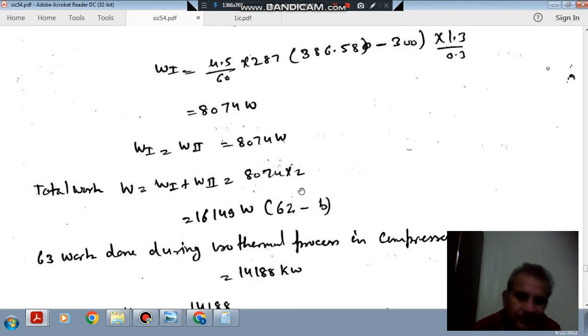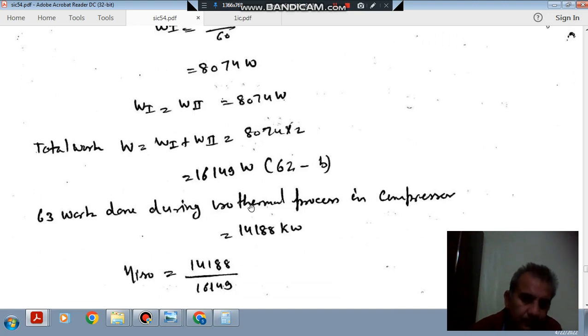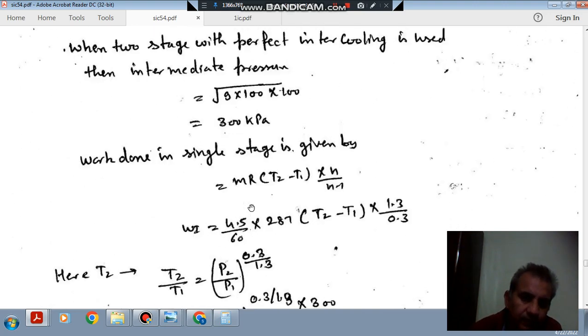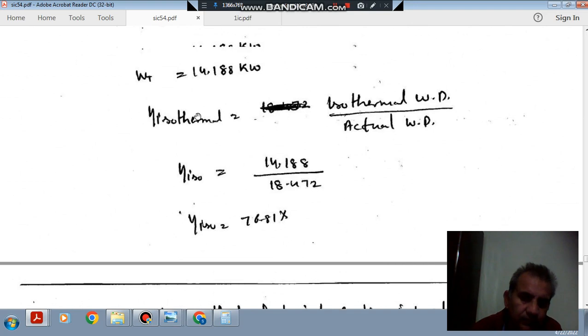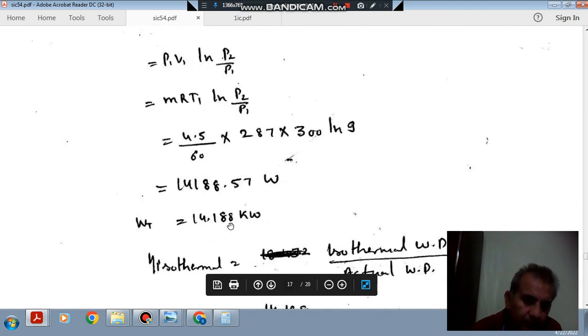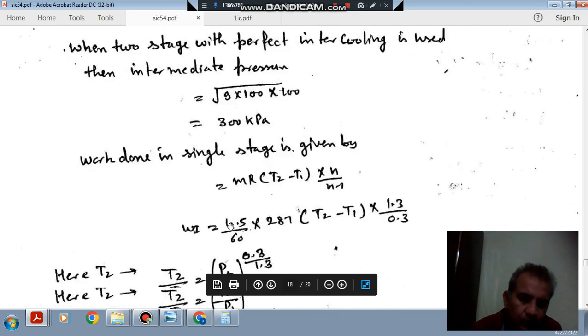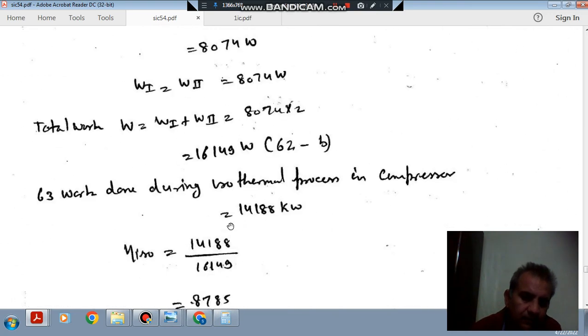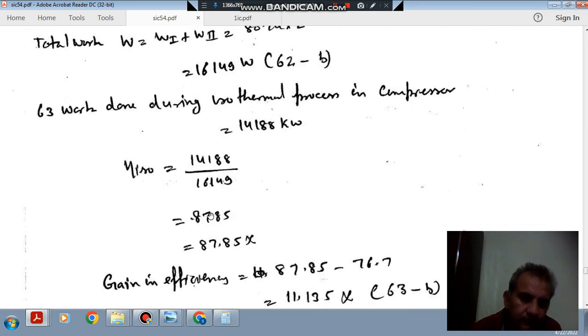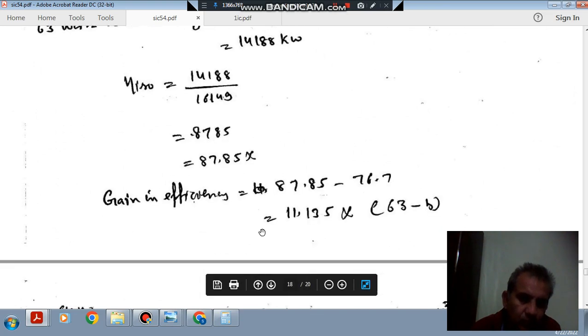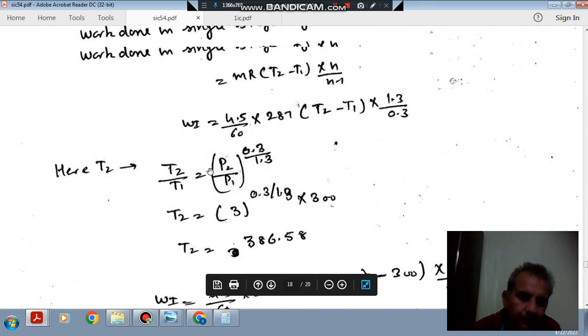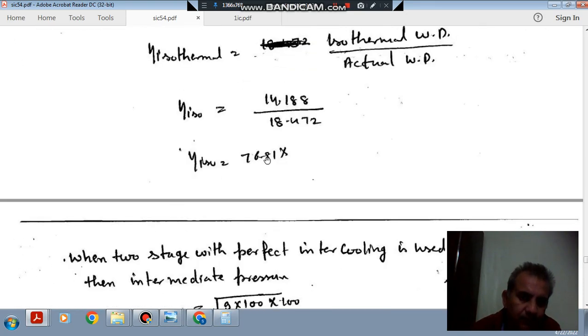For isothermal work done, as you have found, it is 14.188 kW. That will remain the same whether it is single stage or multistage. Isothermal efficiency will be isothermal work done divided by actual work done, which is 87.85%. Previously the efficiency was 76.85%.